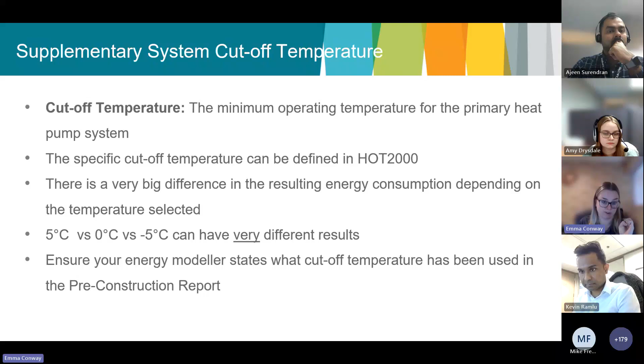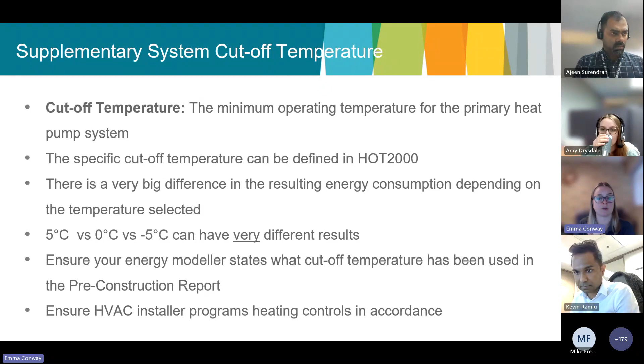The HVAC installer is the one programming the controls. So if your energy advisor states a -5 or 0 degrees Celsius cutoff temperature, and your HVAC installer isn't aware of that and sets it to 2 or 5 degrees Celsius, now the home isn't performing as designed. This is very important to understand, because it has large implications for our step code compliance, and also our zero carbon step code compliance.